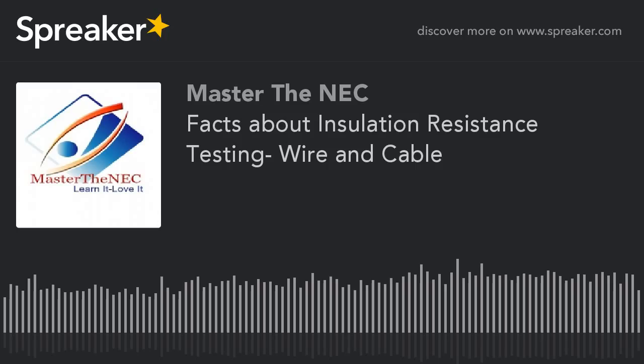However, I routinely see companies all over the country doing this, and I guess that's what I'm doing here. I'm probably one of the first in the industry actually exposing this dirty little secret. The dirty little secret is that you cannot test insulated conductors to insulated conductors and get an accurate reading for insulation resistance. Now, in a non-metallic cable, let's take a tray cable, where all of the inner conductors, which incidentally are the same inner conductors as if you were to buy individual wire on a reel, are just cabled and put inside of a non-metallic product, there's no real way to check insulated conductor to insulated conductor.